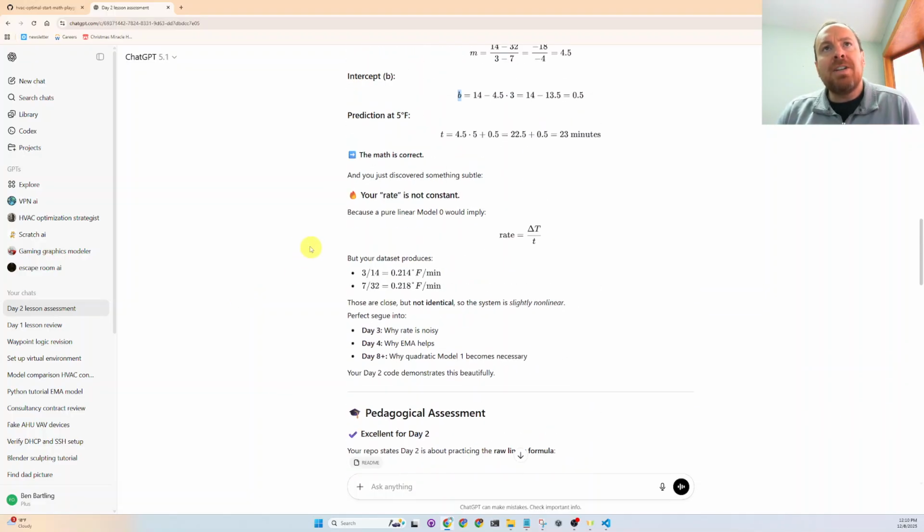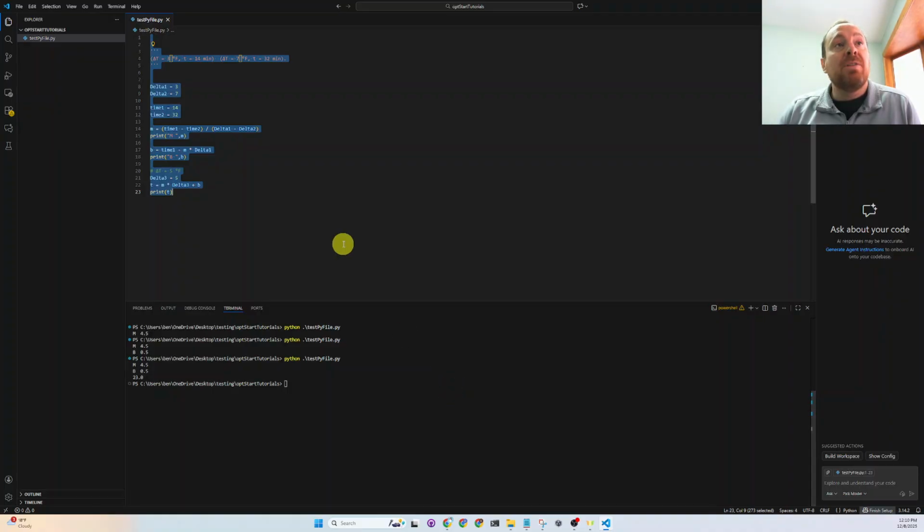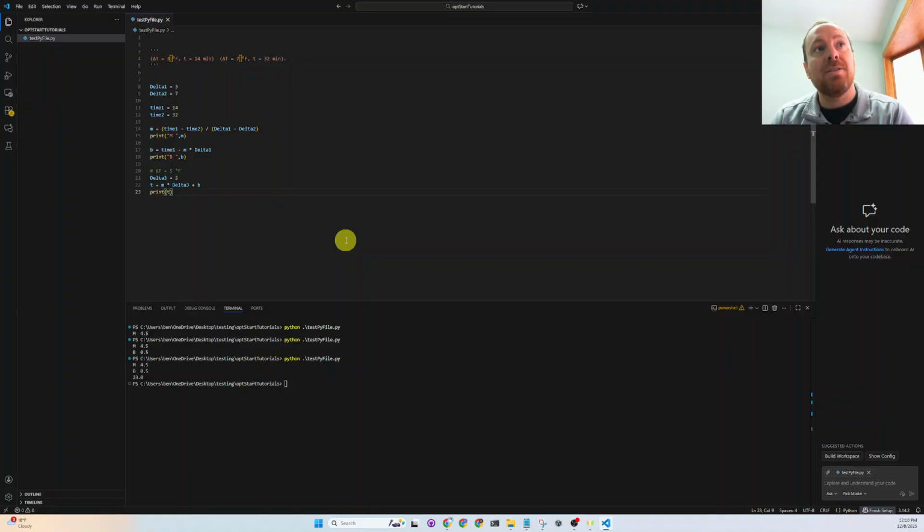And technically, on the last video we decompiled the Tridium optimal start block, and this is pretty much the math behind what's built into Tridium's Niagara control. It's just yesterday's data, the last performance, and basically fine-tuning it based on only one day of data. But these more complicated models will start having 10 days' worth of data, and in theory will get better results.